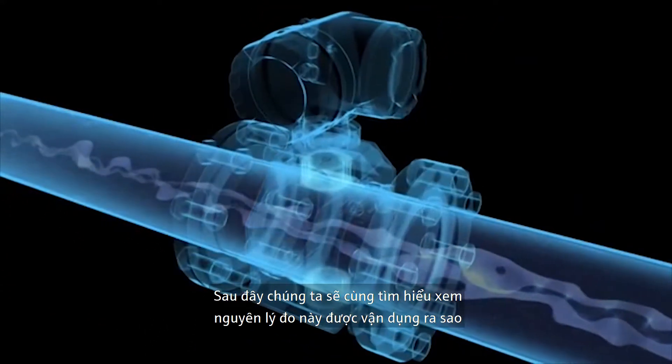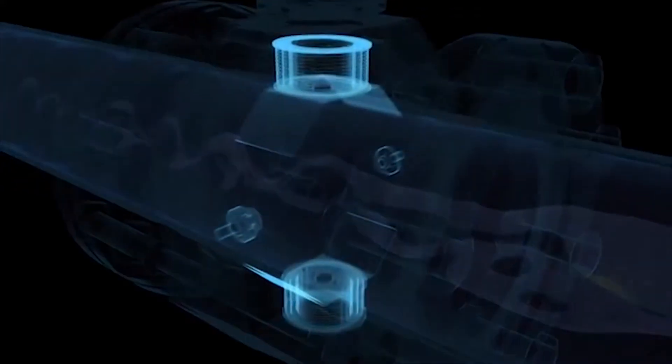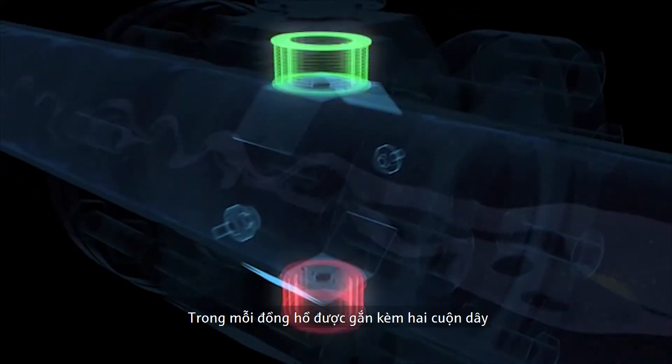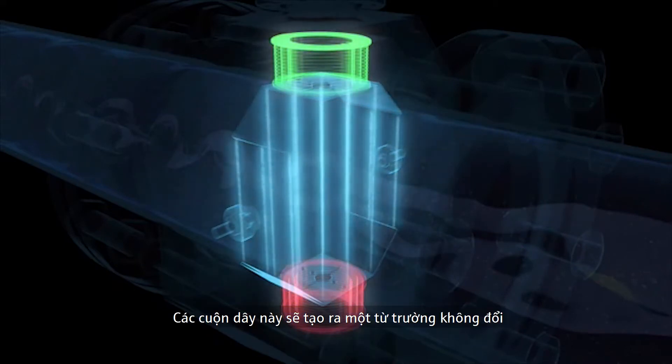Let's take a closer look at how this measurement method works. Two field coils are located inside each electromagnetic flow meter. With the help of pole shoes, these coils generate a constant magnetic field over the entire cross section of the measuring tube.